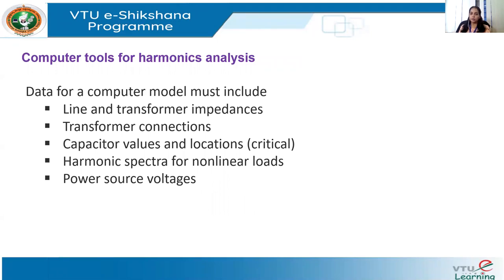To use any computer tools commonly available to study and analyze harmonics, the analyst must describe the system configuration and circuit configuration. They should know the details about the load and the sources. Before doing the computer analysis, we need to collect some data to be inputted into the system. We need line and transformer impedances, transformer connections — whether delta or star — and the values and locations of capacitor banks.